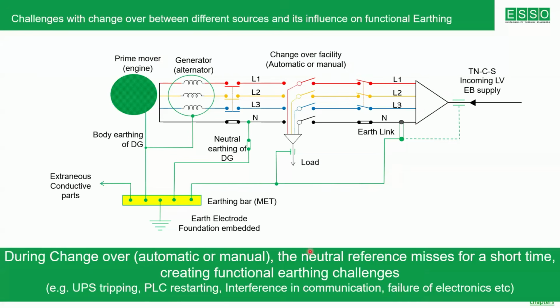Now the challenge is, during the changeover, which can be automatic or manual, the neutral reference goes missing for a short time. Because the neutral is missing, the zero reference for the electronic equipment is missing for a short time. Now, if you have class 1 biomedical equipment which has a communication facility, and if the equipment is using neutral as the reference of the electronic equipment, the challenge starts because of the changeover. UPSs may trip, PLCs will restart, interference in communication will happen, failure of electronic equipment will happen during this particular changeover.